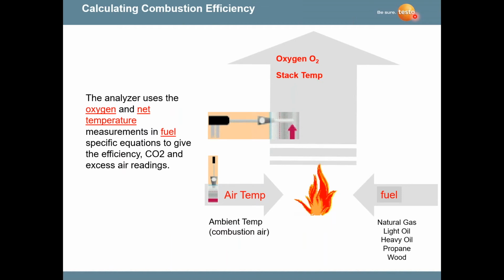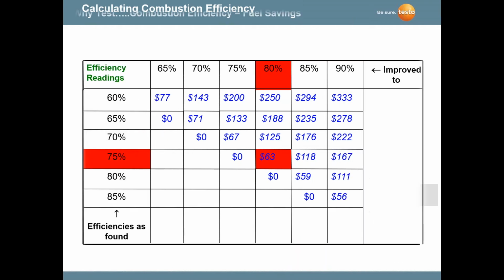The last thing here is combustion efficiency. We're checking, we've got the probe in the stack. We're pulling out the oxygen in the stack. We know the stack temperature with a thermocouple. We've got the fuel that we know, and we can calculate the combustion efficiency. And the whole thing with combustion efficiency is fuel savings. If you look at this graph, and this is just an illustration, if you start at 75% and you can increase your combustion efficiency to 80%, you're saving roughly $63 on $1,000 of fuel spent.